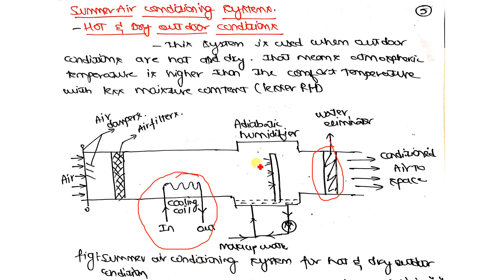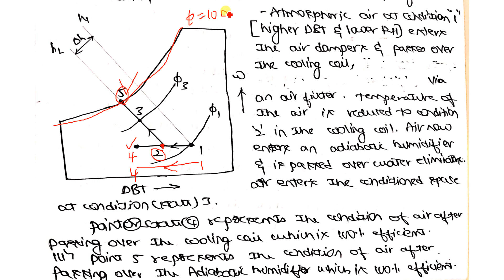So, if it reaches the saturation curve here, then there would be no vapor content in it. Why? Because the relative humidity of this particular thing is 100%. Correct? So, it would not reach here, it would stop here. That is how the adiabatic humidifier works from 2 to 3. So, two processes, guys: 1 to 2 is sensible cooling and 2 to 3 is adiabatic humidification.